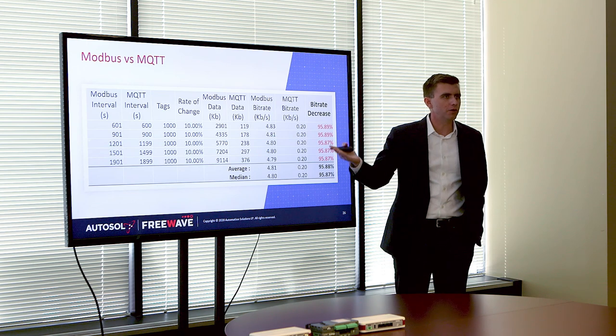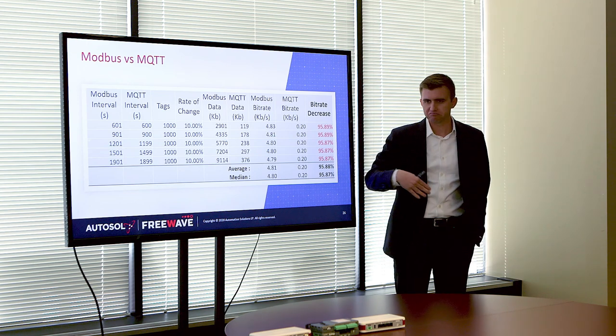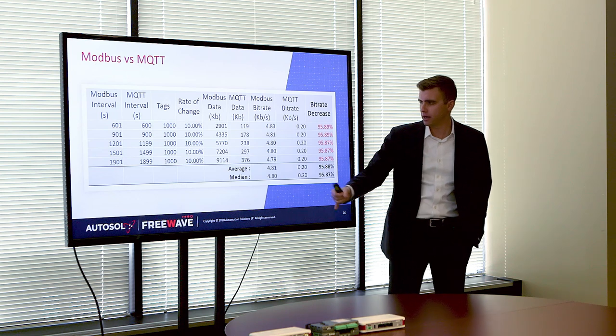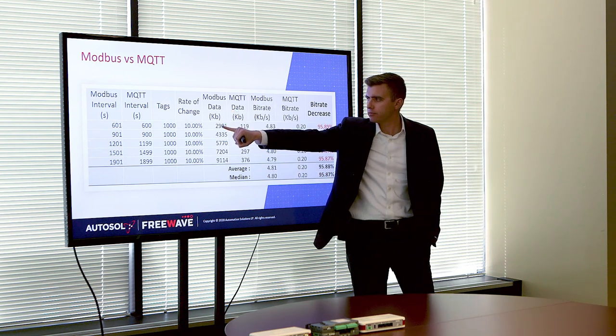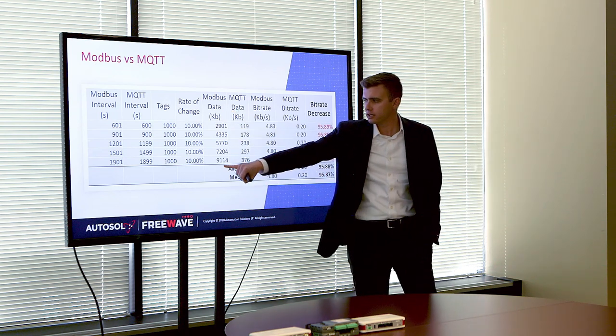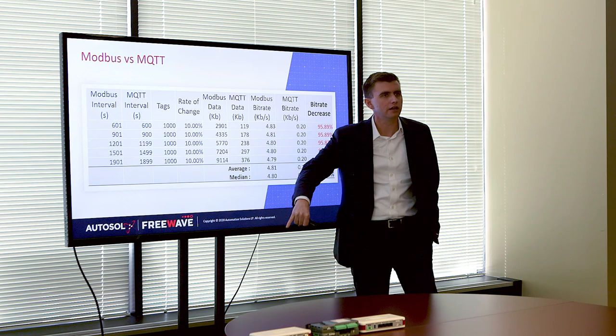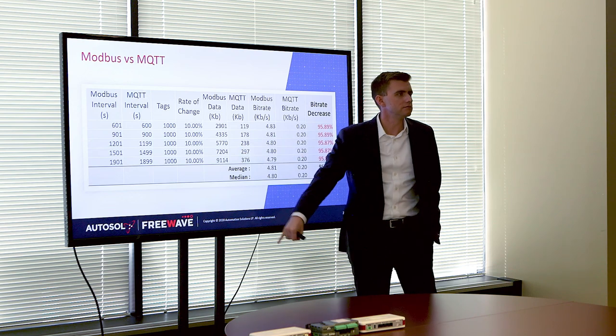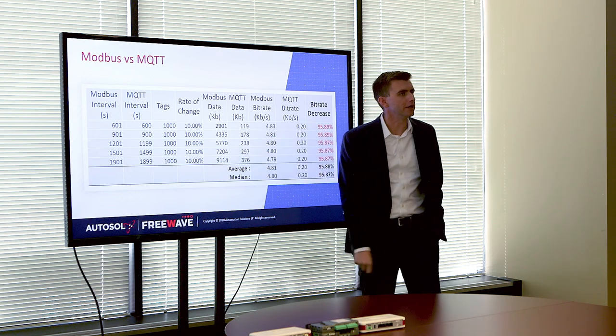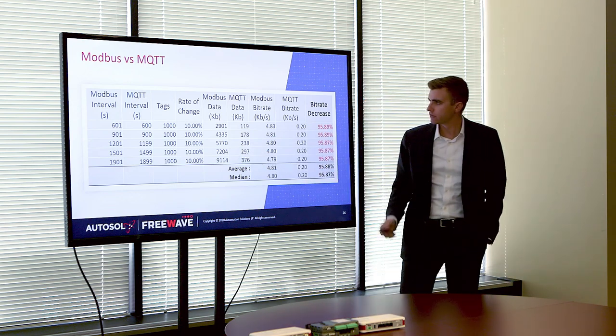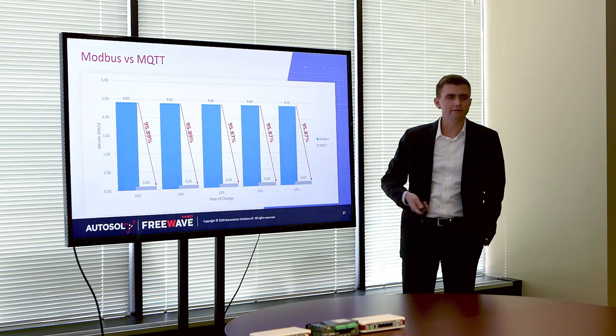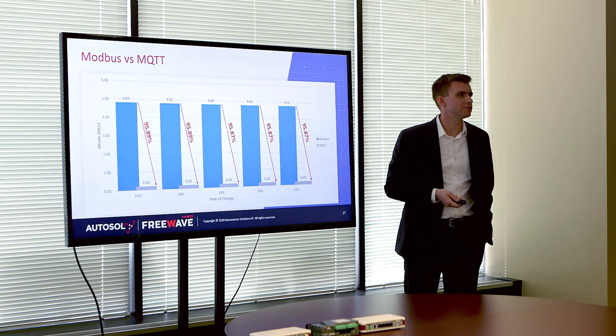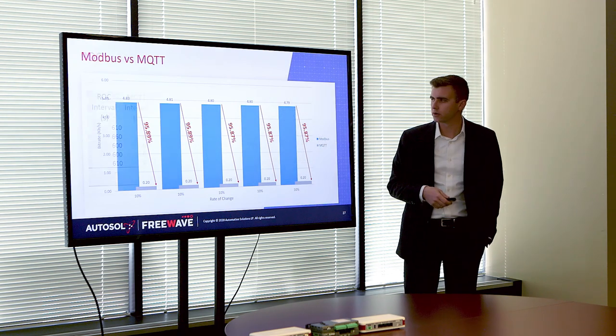Every poll is going to occupy the same amount of data. So Modbus data consumption from 2,900 to 9,100 kilobytes is linear based on how long we're polling. And visualizing that, a 96% reduction of bandwidth consumption across the board.